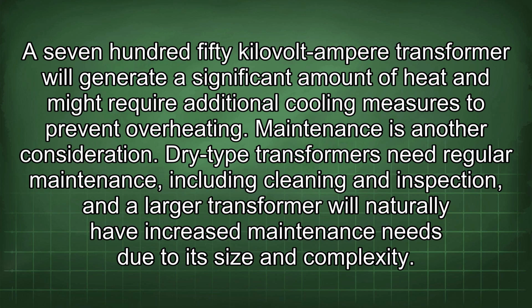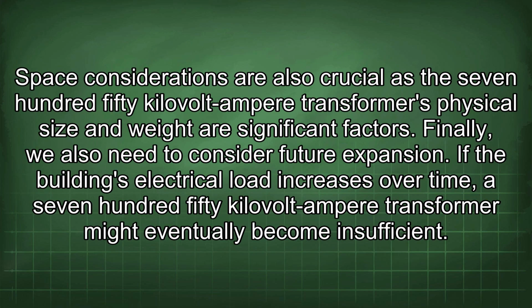overheating. Maintenance is another consideration. Dry-type transformers need regular maintenance, including cleaning and inspection, and a larger transformer will naturally have increased maintenance needs due to its size and complexity. Space considerations are also crucial, as the 750 kVA transformer's physical size and weight are significant factors.